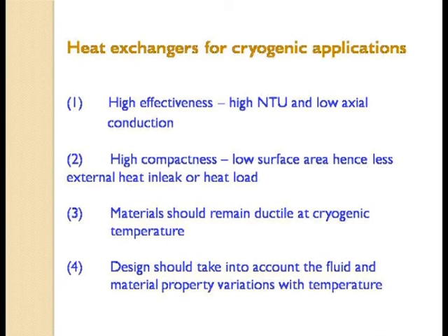And this third one, the aluminum brazed plate fin heat exchanger, can be used in bigger, large plants also, because they have the advantage that they are very compact, with similar performance as the other two heat exchangers, but they need small space and their performance is also much better than the other heat exchangers. So slowly in these bigger industries, bigger plants, this third one, the aluminum brazed plate pin heat exchangers, replace the other types of heat exchangers which are otherwise being used very commonly in industries.